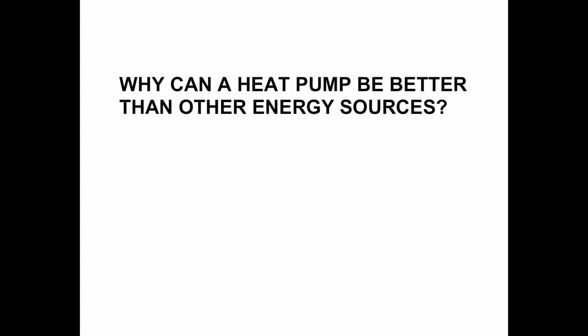So is it true then that at minus 13, there's still heat in the air? There's energy in the air that you can use. You can move it and transfer it through the refrigerant and the phase change of the refrigerant with a compressor and then deliver heat into the space in that manner. So even though it's really cold for us, there's still energy in that air that can be used. So we're still getting something. Yes, absolutely. We just can't get the house to 70.